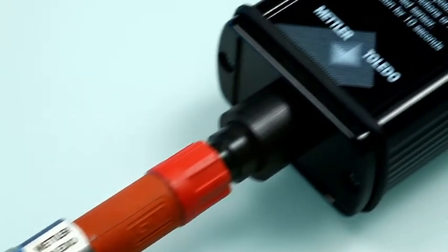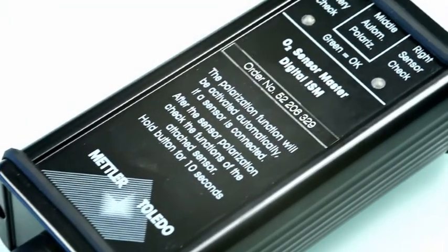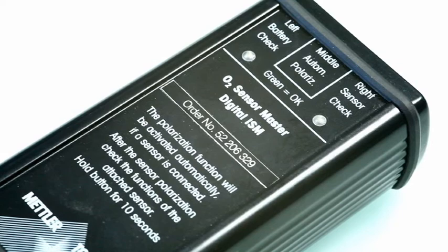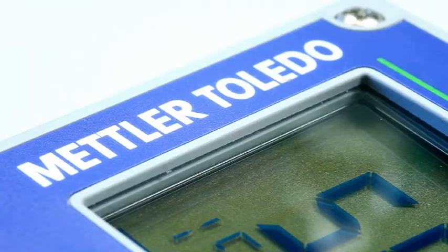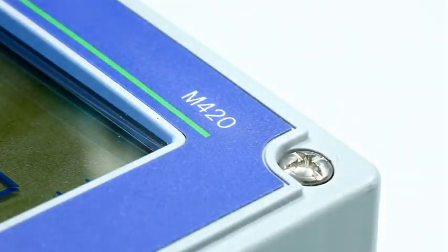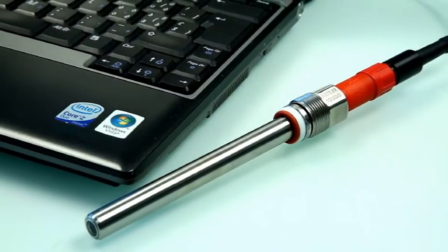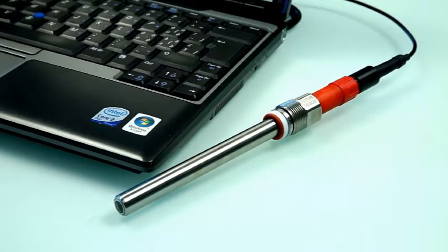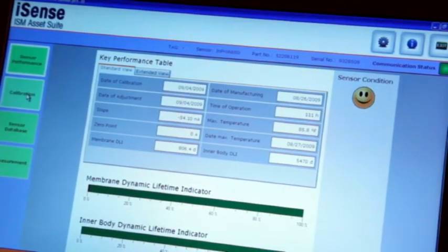For polarizing the sensor, three options are available. You can use our polarizer and checking unit called SensorMaster. You can use the transmitter the sensor will be connected to during operation. Or you can polarize it on iSense, the PC-based asset suite that allows you to monitor the health status of your sensor.